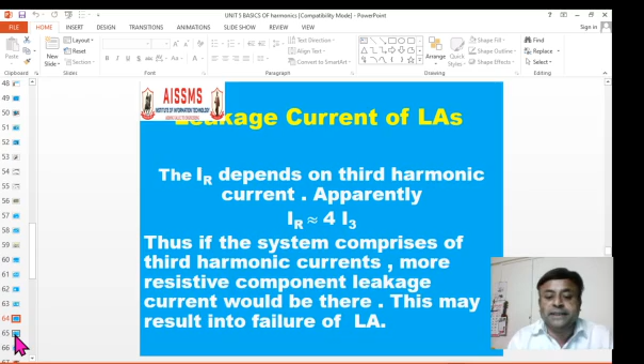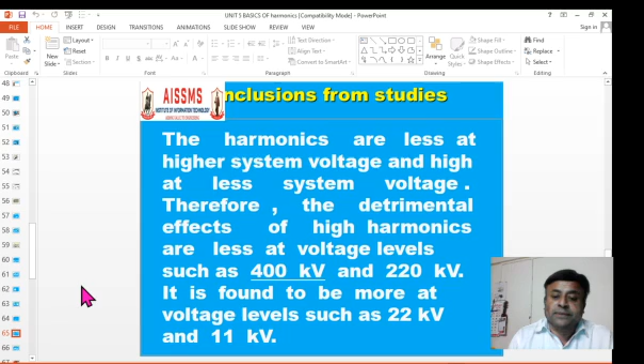It was also seen in some experiments that at extra high voltage, EHV, or ultra high voltage, UHV, the harmonics are lesser. At the same time, they are more at 11 kV, 22 kV, and 33 kV levels. That was one of the findings. Another important finding is because of distance. Distance and harmonics are inversely proportional. Harmonics are more near the nonlinear load, and as you go away from the nonlinear load, there is a reduction in the harmonics.